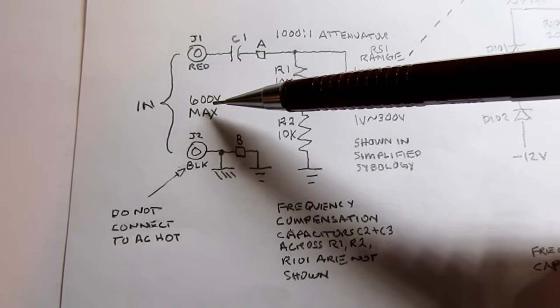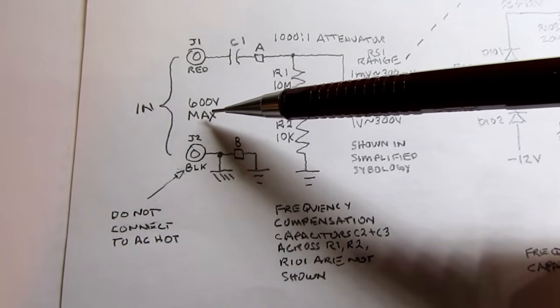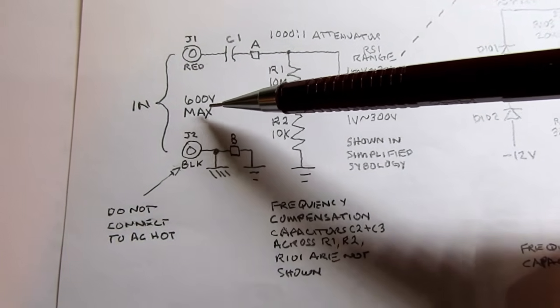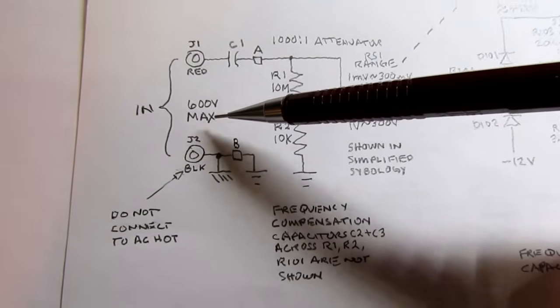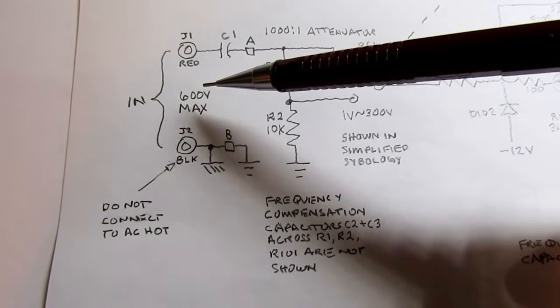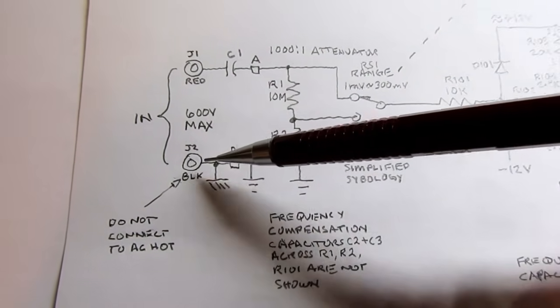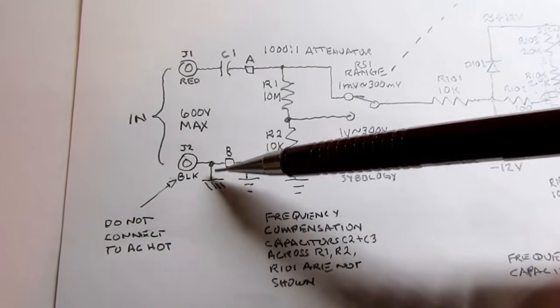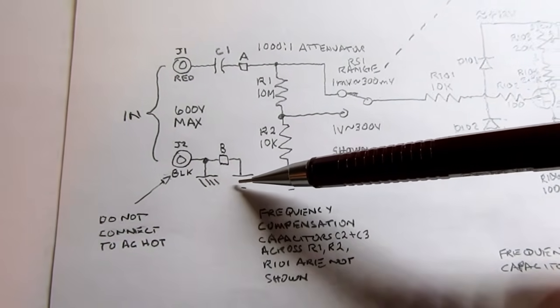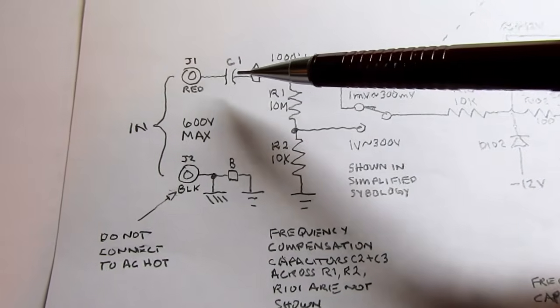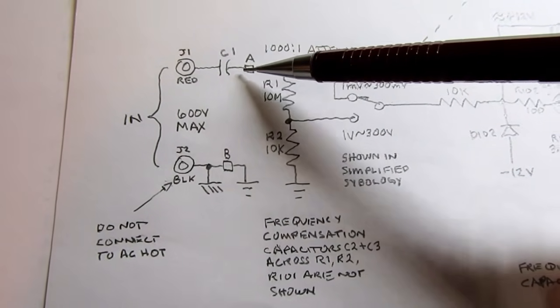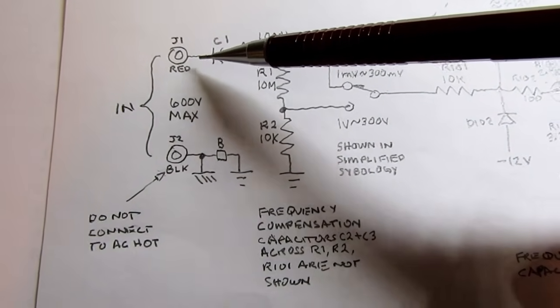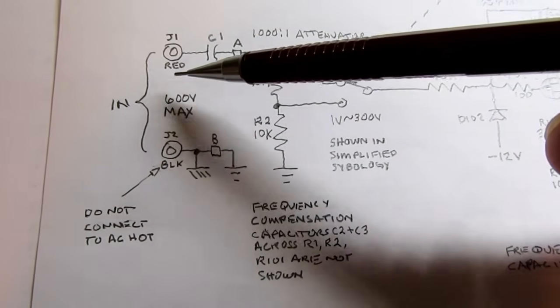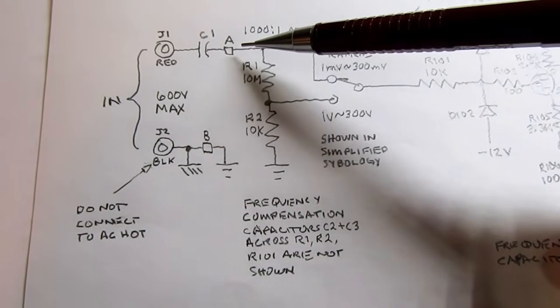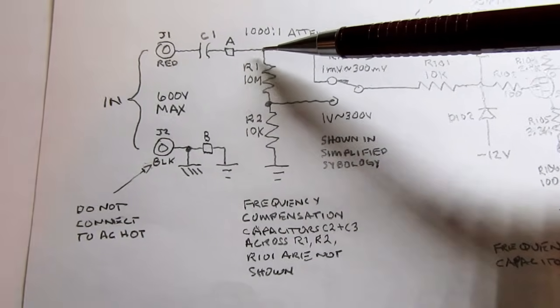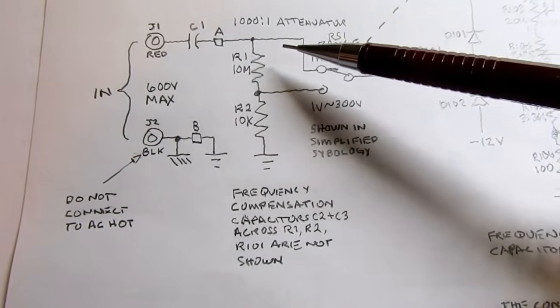The highest full-scale range on the meter is 300 volts, but the circuit is designed to withstand up to 600 volts without damage. So it's 600 volts max, 300 volts useful. This terminal is connected, besides to chassis ground, also to circuit ground. And this terminal goes through a capacitor. This blocks any DC component of the signal being measured, so only AC gets through, and since it's an AC meter, all we want to look at is the AC portion.